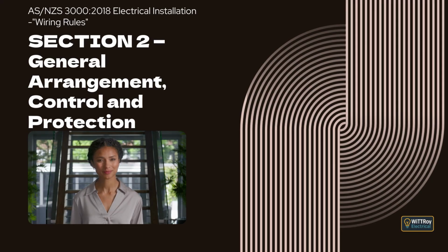They are protection for final subcircuits, especially in places where a fire would be very dangerous. Common places where AFDDs are useful include any area where people sleep, places where flammable materials are stored or processed, buildings made from combustible materials such as timber, and any structure where fire can spread quickly. The standard explains that AFDDs are an extra layer of safety. They do not replace other protective requirements.